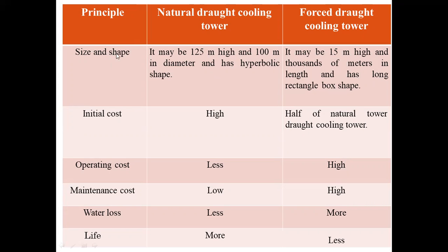If we are talking about size and shape, natural draft cooling tower may be 125-meter high and 100-meter in diameter and hyperbolic shape, while for the same capacity forced draft cooling tower may be 15-meter high and 1000 meter in length, has long rectangular box shape. Initial cost of natural draft cooling tower is high, while for the mechanical cooling tower is almost half. Operating cost is less, while it is high; maintenance cost is low, while it is very high. Water loss is less, where it is more. Life is more, where life is less.